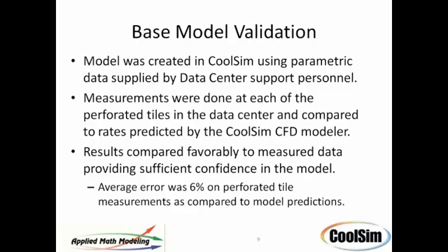And we've defined the supply temperature. That was a boundary condition set by measurement at 55 degrees. And the IT loads for the racks were measured, so we put those in. So that means that we got a pretty solid model, Liz. Wouldn't you think? I would say so. Yeah, very much so.